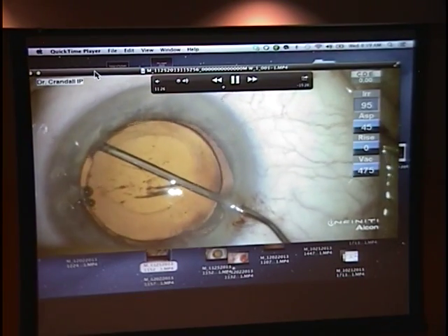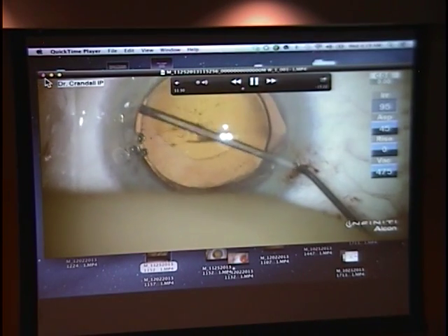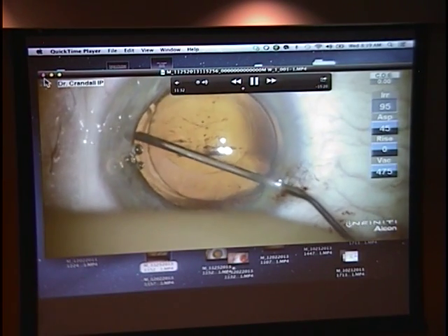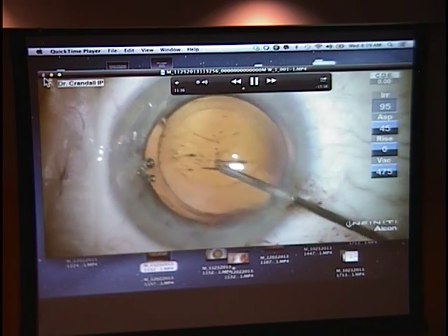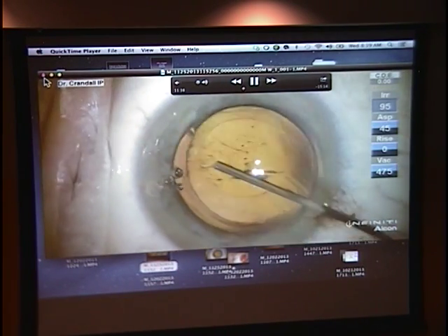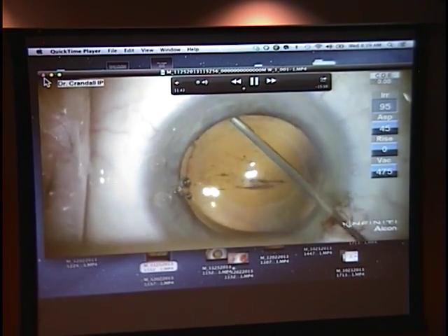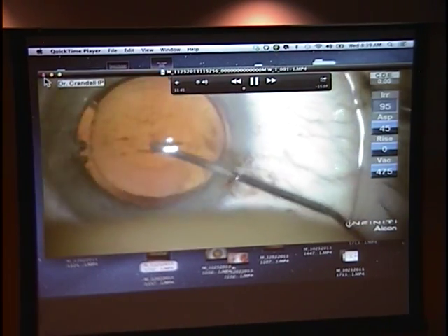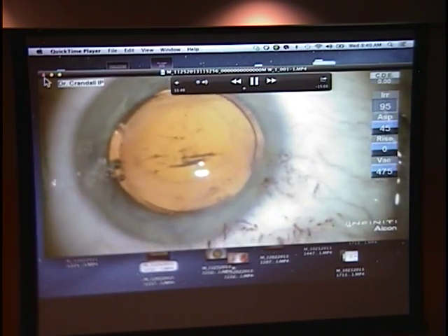And I'm going to let Nick talk about this. We don't need to watch the rest of this. I'll show this. Anybody is available to get that out. But one of the things is do not pull to the center of the thing. Everybody wants to get the lens out by pulling this way. What you have to do is use two instruments and turn counterclockwise so that it pops out of its thing. And I've got a set of videos if anybody wants to see those.